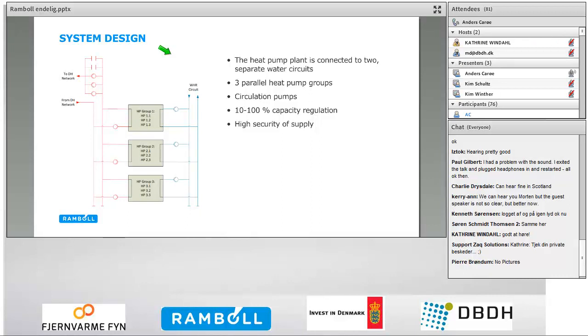Each of the 3 groups has dedicated circulation pumps on the waste heat recovery side and the district heating side, which ensures accurate control of water flows and temperatures. This particular design of the plant means that we can regulate fully between 10 and 100% capacity without significant reduction in efficiency. And at the same time, it guarantees a high security of supply since a component failure in one group will not affect the other 2 groups.